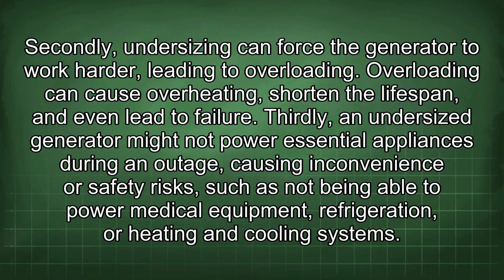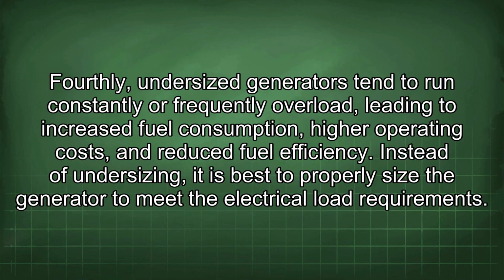Thirdly, an undersized generator might not power essential appliances during an outage, causing inconvenience or safety risks such as not being able to power medical equipment, refrigeration, or heating and cooling systems. Fourthly, undersized generators tend to run constantly or frequently overload, leading to increased fuel consumption, higher operating costs, and reduced fuel efficiency. Instead of undersizing, it is best to properly size the generator to meet the electrical load requirements.